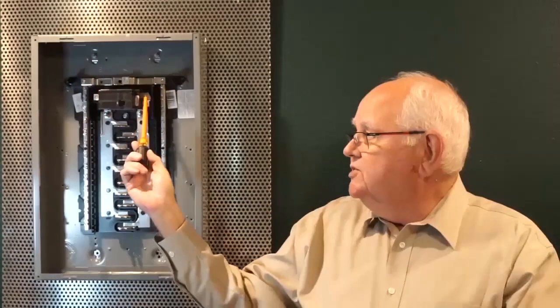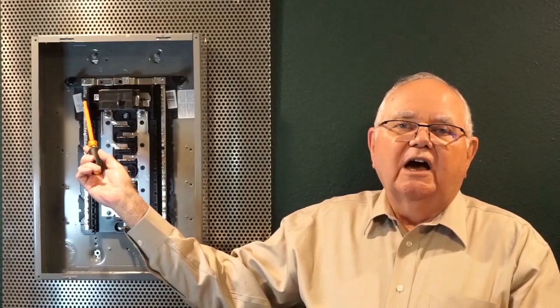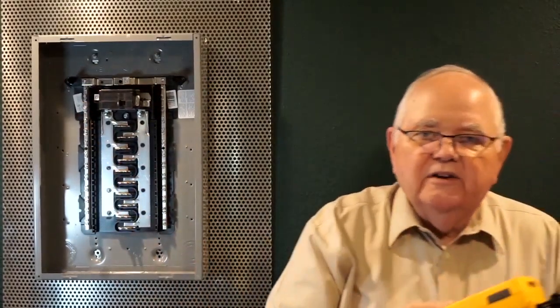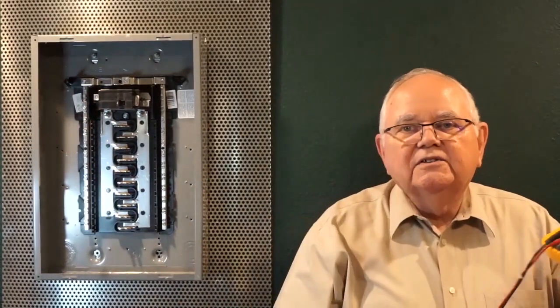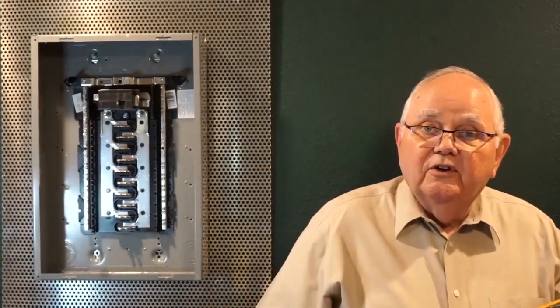So if we've de-energized the upstream breaker and we want to verify that these 2 terminals bringing the power into our equipment are in fact de-energized, the first thing we're going to do is, of course, inspect our meter, make sure the meter and the test leads themselves are safe to use. And then we want to use a 3-step method.